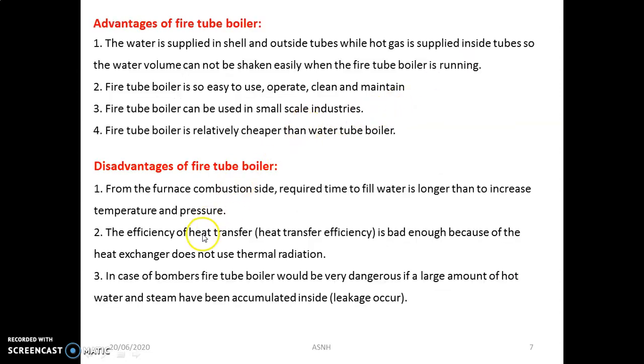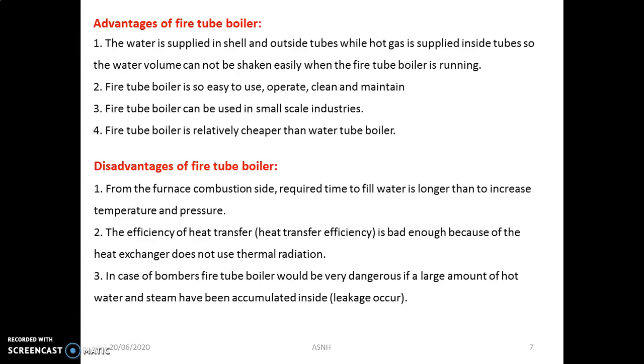These are the advantages and disadvantages of the fire tube boiler. The water is supplied in the shell and outside the tubes, while hot gases are supplied inside the tubes, so the water volume cannot be shaken easily when the boiler is running. The fire tube boiler is easy to use, operate, clean, and maintain. As far as disadvantages are concerned, the efficiency of heat transfer is poor because heat exchange is very poor and there is limited thermal radiation. Also, there is a furnace combustion limitation.